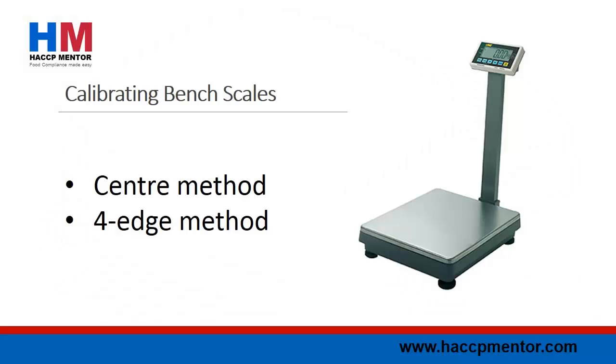Calibrating Bench Scales: When you perform internal calibration of your digital bench scales, you should be using two different methods to test. This includes the 4-edge method and the center method.